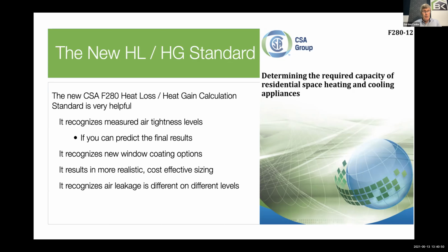So I mentioned F280. I'll just move along here a little bit. The new heat loss heat gain standard as of 2012 recognizes measured air tightness, which is great. Obviously, you have to be able to predict, and people ask me, how do I predict? Well, builders have a pretty good track record. Pick a conservative number. I always get under 2 air changes. Give that to your HVAC designer. That's fine. The new heat loss heat gain gives a much better accounting of new windows and new coating options. We would say it's much more realistic and cost effective, and it does recognize air leakage on different levels. It recognizes the fact that rooms on the main floor need more heat than rooms on the third floor, for example. So that's kind of useful.